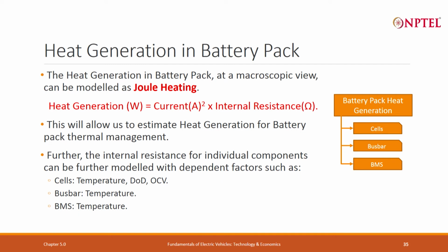One parameter is current, depending on the charge and discharge rate. The other parameter is internal resistance, which is not constant — it depends on OCV, depth of discharge, and temperature. Similarly for the bus bar, resistance changes with temperature, and for the BMS, MOSFETs, or contactors, resistance also changes with temperature. So to accurately estimate heat generation, we also need to consider the temperature at which these components are working.